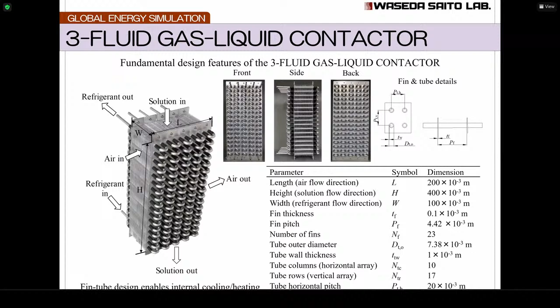There is a problem, because this ionic liquid has a very, very high viscosity. So when we try to supply this liquid desiccant onto the fin plate, normally, when we just use water or something, a very simple, very thin, very good falling film is produced on the outside. But this ionic liquid has a very, very high viscosity. Sometimes this kind of dry area occurs, just like this. The liquid desiccant makes this kind of rivulet. So many dry patches, so many dry areas occur. That's why heat and mass transfer performance decreases greatly.